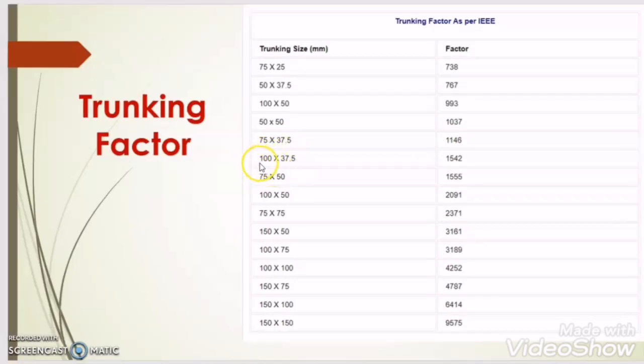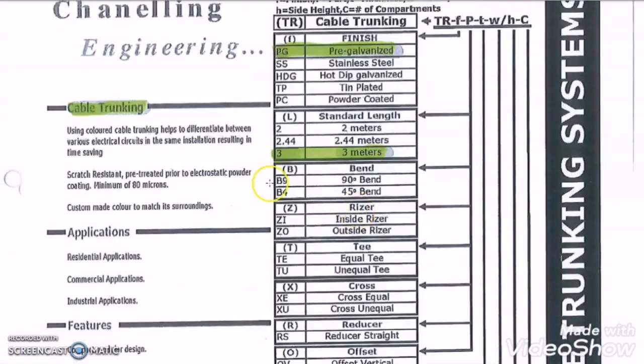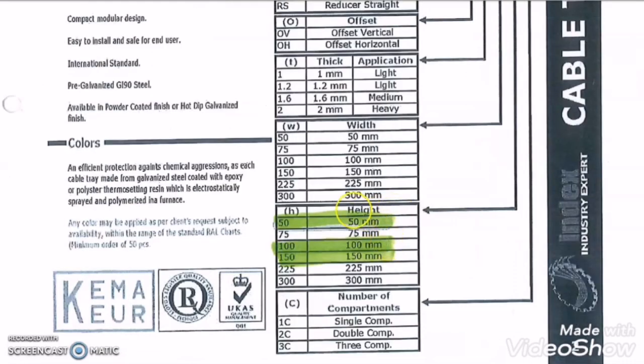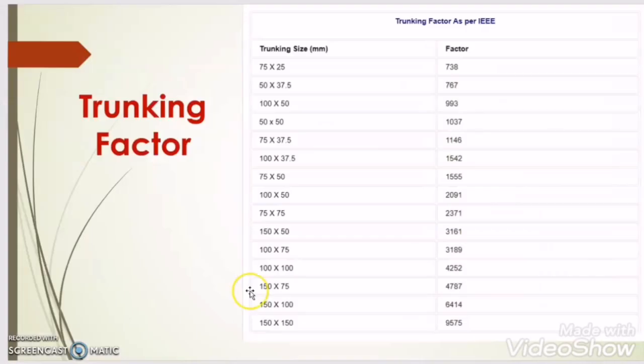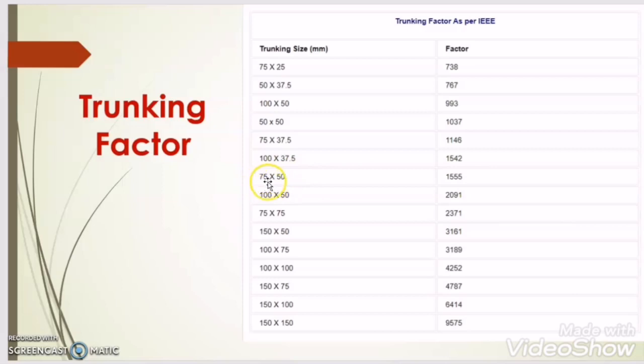But I cannot choose a trunking of size 100 x 37.5, because in my project the approved trunking is pre-galvanized type with heights of 50mm, 100mm, and 150mm. I cannot go for a trunking with a height of 37.5mm. In that case I will go for the next higher size trunking. Since 75 x 50 is approved in my project — the height of 50mm is approved — I will select the trunking size of 75 x 50. Hope you understood this.